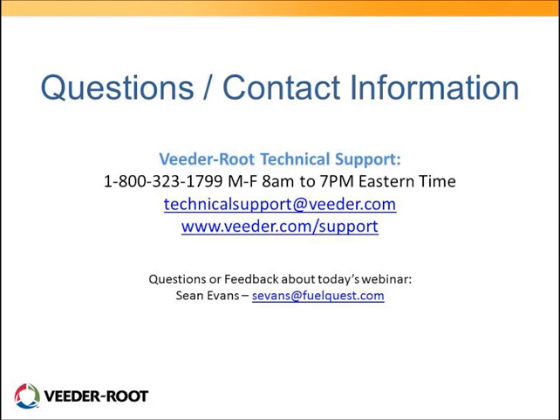Now we've got one more question here. What is the most common sensor used for interstitial monitoring? Okay, so based on the profile of the tanks out there, the majority of the tanks we see today are dry interstitial double wall tanks. They typically use what we call a simple sensor on the Veeder-Root side, and it's a float style switch that detects liquid. We do have sensors that can go in that same space that can detect water or fuel if that's important to the end user.